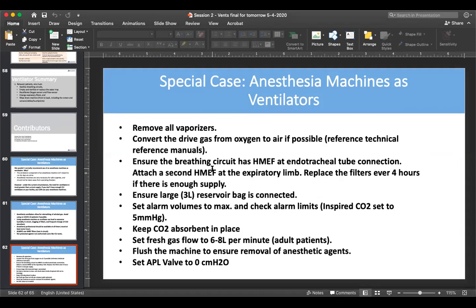You want to ensure that the CO2 absorbent is in place. Part of the reason is because the anesthesia circuits are designed for rebreathing, right? Because you want to minimize waste. And so if they're rebreathing, you will need to filter out the carbon dioxide from the circuit. But you do not have to replace the soda lime between each patient, as long as you use 2 HMEF filters in the circuit prior to that.